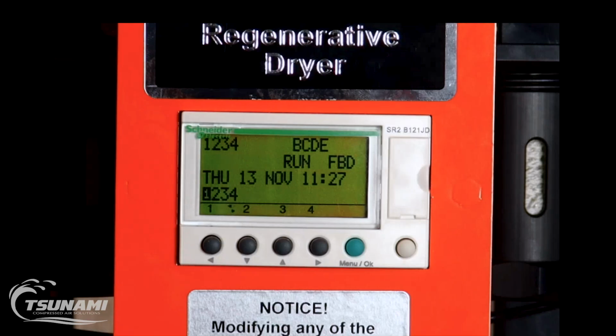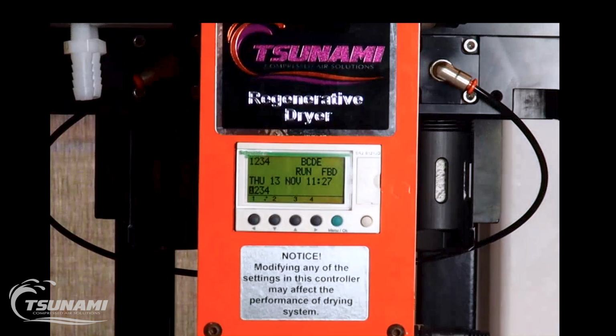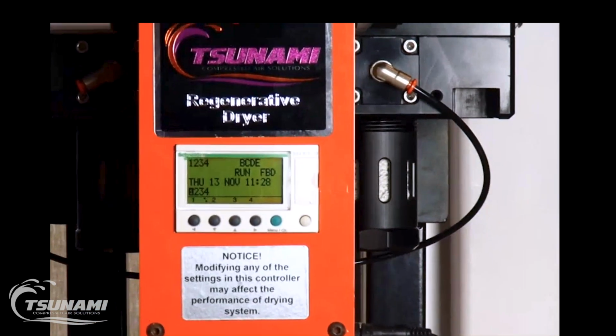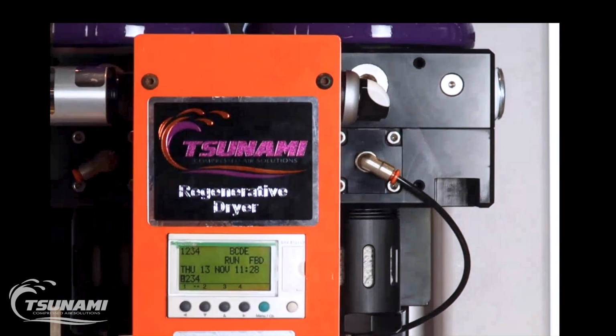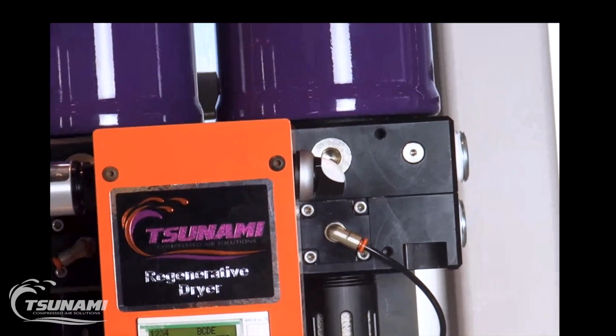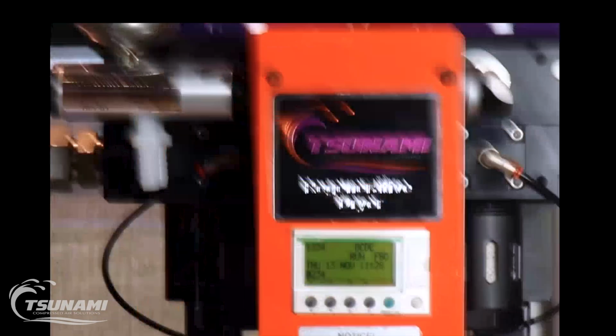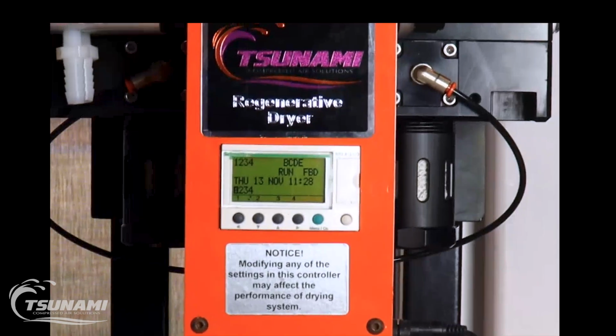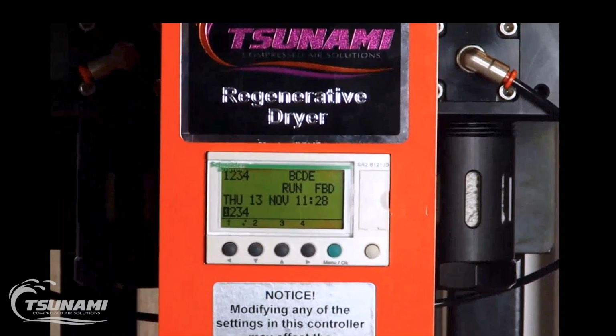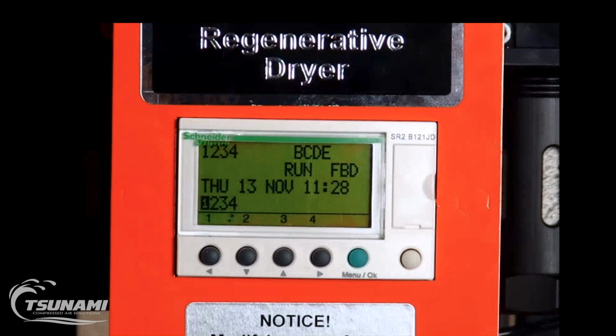Now, as I said, these systems are set up so that we can have digital or analog signals coming into it. On this display PLC, you can't exactly see it, but we are plumbed in to where we have it set up. I'll zoom out real quick here. So on the side of this PLC, we have a couple switches up at the top, and those switches simulate inputs that might be coming from a compressor or from a piece of equipment that we want to utilize for a signal to tell us whether or not we want our dryer running. So what I'm going to do now is walk through how that works.